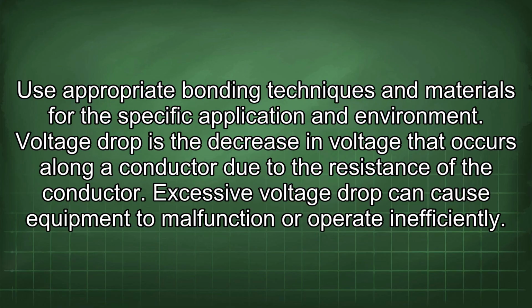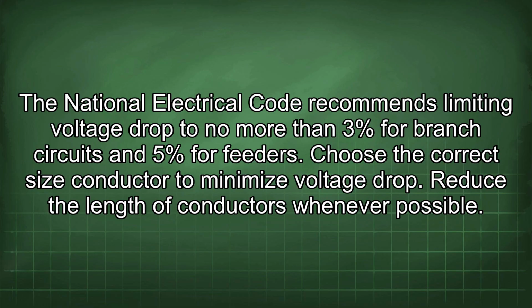Voltage drop is the decrease in voltage that occurs along a conductor due to the resistance of the conductor. Excessive voltage drop can cause equipment to malfunction or operate inefficiently. The National Electrical Code recommends limiting voltage drop to no more than 3% for branch circuits and 5% for feeders.